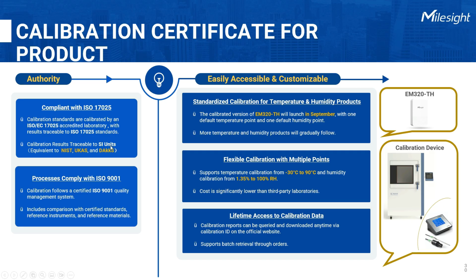After that, the customer will receive a calibration report issued by a CNAS-certified lab. In simple terms, before the product leaves the factory, we make sure the temperature and humidity sensors are tested against internationally recognized ISO 17025 standards. This gives customers the confidence that the readings are accurate.